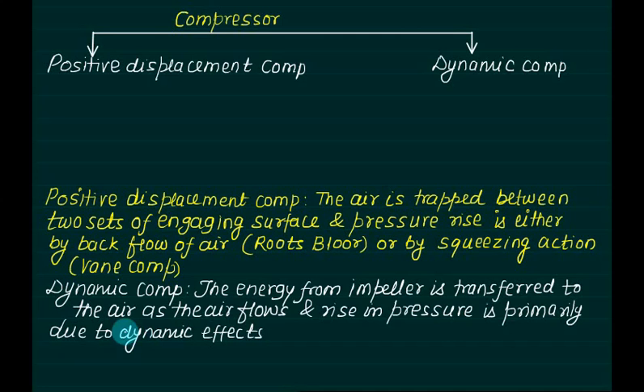In the case of dynamic compressor, the energy from impeller is transferred to the air as the air flows and rise in pressure is primarily due to dynamic effect. In this case, air is not trapped in a specific boundary but it flows continuously and steadily through the machine.